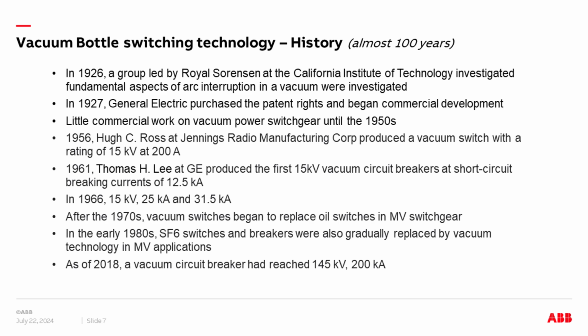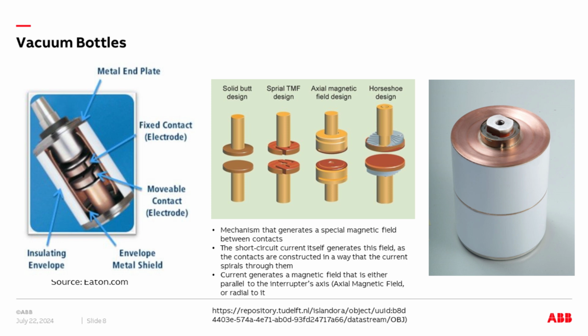Then you can see as we go through the 60s and 70s, we start to see more applications in switchgear. And then into the 80s, replacement for SF6, gradually in some applications, medium voltage. And then finally, 2018, capability reached all the way up to 145 kV, 200 kA. So bottle technology has evolved quite a bit.